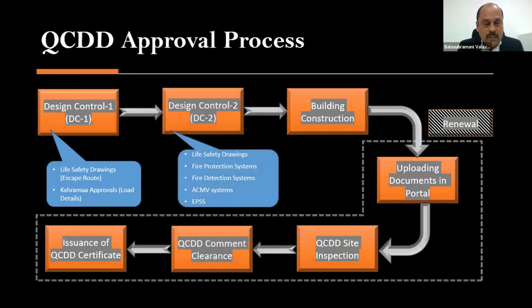What are those approval processes? Some of you might be aware there is DC1, design control 1. It covers the life safety drawing and first escape route. You have to get an approval, and Kahramaa approvals with respect to load details: what all the equipment is going to be placed, every detail, different kinds of equipment, electrical, mechanical. You have to get an approval. And for the subsequent approval, you also have to submit DC2, which covers the life safety drawing, fire protection system, fire detection system, AC, mechanical ventilation, and EPSs, emergency power supply system. So these two approvals you have to obtain.